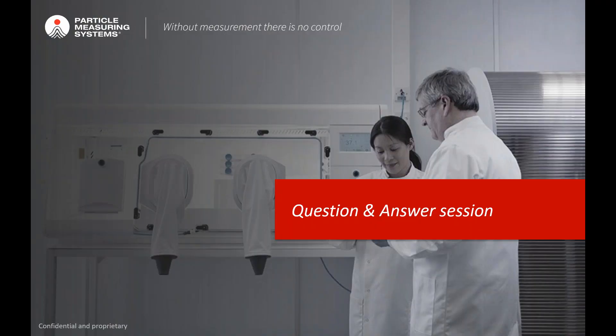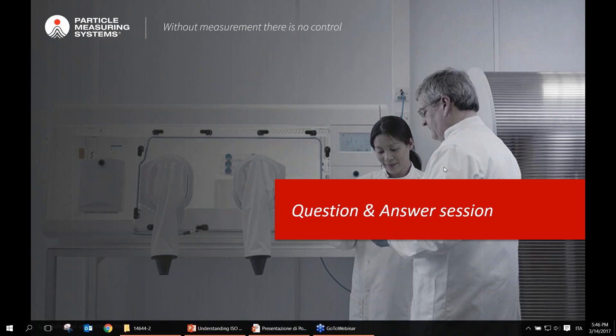Now for the question and answer session. First question: Can I omit the annual clean room classification required by ISO 14644 Part 1 if I run continuous monitoring? No. Clean room monitoring cannot replace classification performed on an annual or semi-annual basis. The classification process dictated by ISO 14644 Part 1 must be performed in combination with other equipment tests, such as HVAC system tests described in ISO 14644 Part 3.